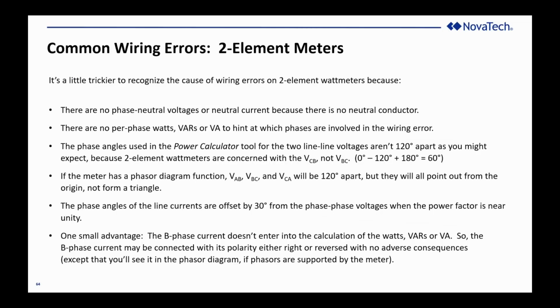Now we move to two-element meters. I want to at least take a minute to recognize that it's harder to determine what you did wrong from a two-element wattmeter than it is from a three-element wattmeter. Why is that? Well, there's no neutral current. There's no phase to neutral voltage. There's no per phase watts. And if you were to plot the phase angles, you're going to see a 60-degree angle between the two voltages that come in instead of 120 degrees. And you're going to see a 30-degree phase angle between the voltage and the current when you have a good power factor. All of these things are counterintuitive when you're trying to figure out how did I wire it, what should I be seeing, and how did I wire it wrong?